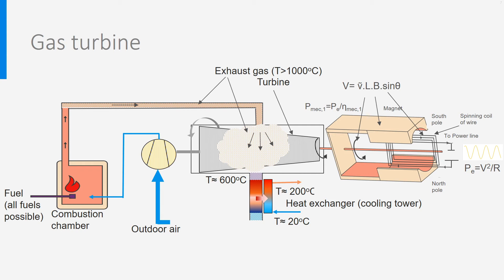Of course, there are all kinds of filters installed nowadays, but the CO2 still goes out. But here too, green fuels can be used like hydrogen. There may also be a heat exchanger, generally coupled to a cooling tower, and placed at the exhaust side of the turbine, like you see on the figure. It can this way recover heat that can be used somewhere else, for instance for district heating, or to further preheat the compressed air before it comes into the combustion chamber.